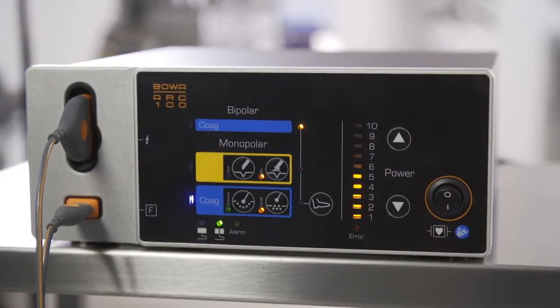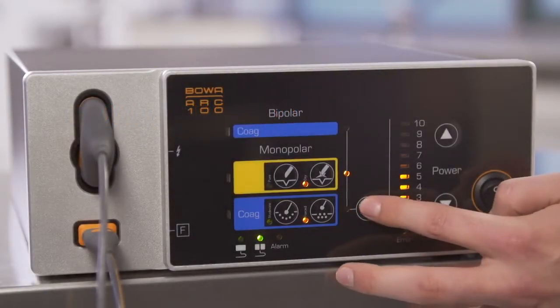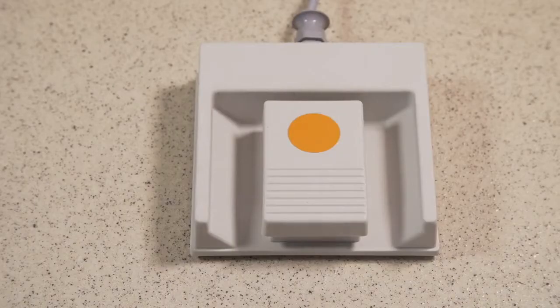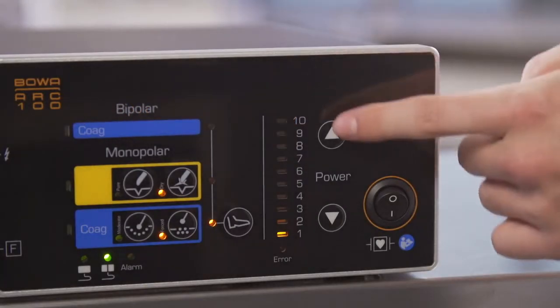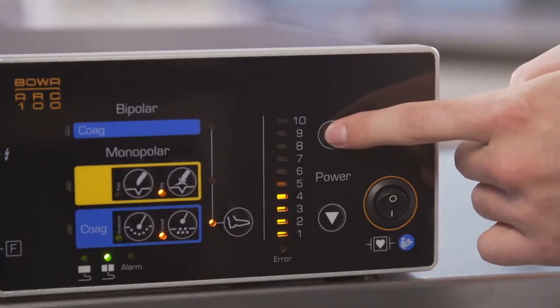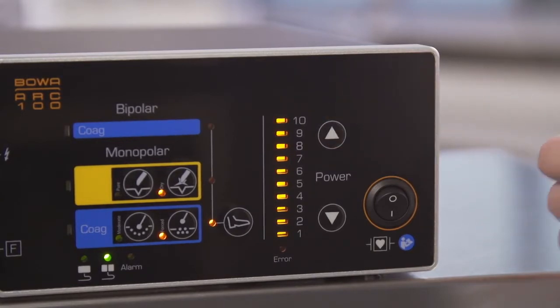The active mode is indicated by the corresponding LED next to the selected mode selection button. Bipolar coagulation is easily called up by assigning the foot switch. The power of the applied current can be set using the arrow keys. 10 corresponds to the full power of 100 watts.